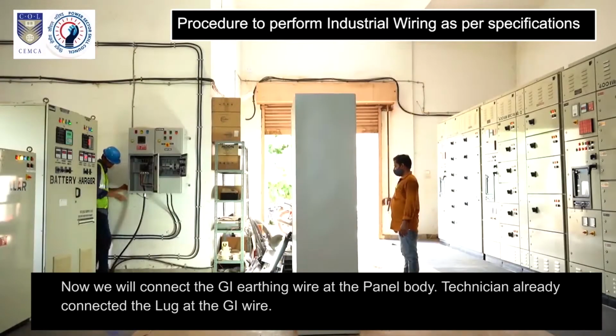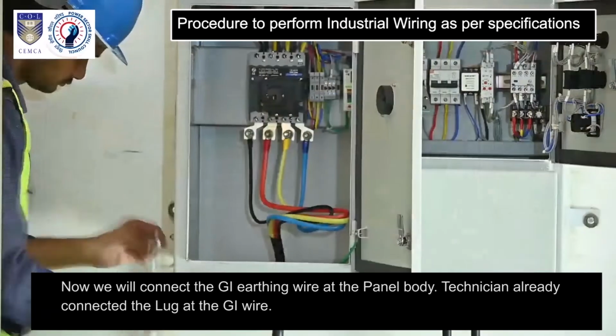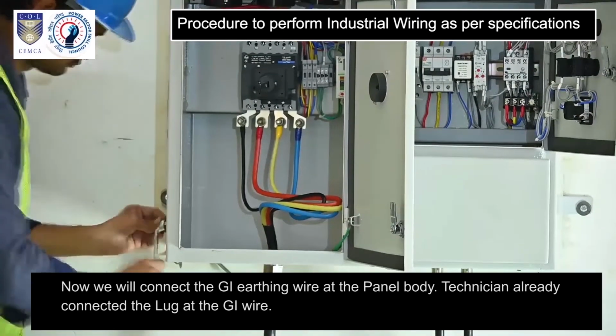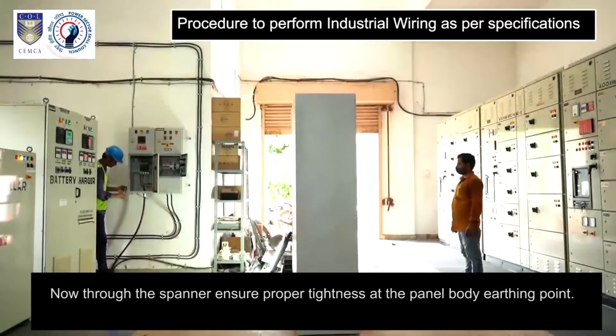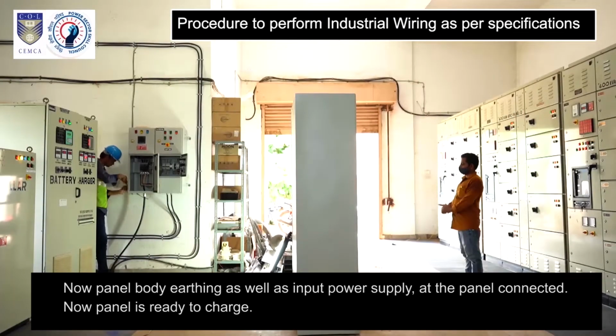Now we will connect the GI earthing wire at the panel body. Technician already connected the lug at the GI wire. Now through the spanner, ensure proper tightness at the panel body earthing point. Now panel body earthing as well as input power supply at the panel are connected. Now panel is ready to charge.